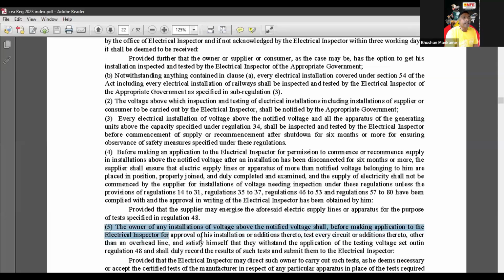It states that the owner of an installation above notified voltage, before making an application to the electrical inspector, or if the installation has an additional electrical arrangement, every circuit of this installation above 650 volts that is going to be energized, and every circuit and addition other than overhead lines, must be tested to withstand the application's testing voltage set out in regulation 48.